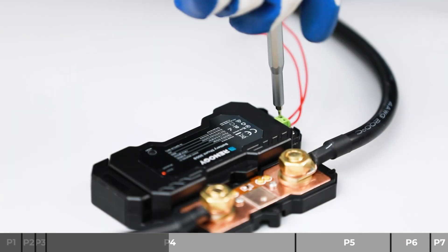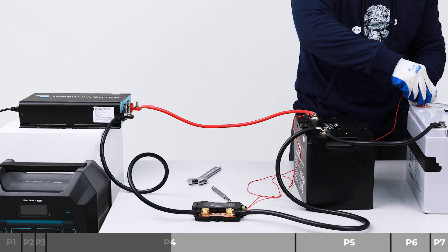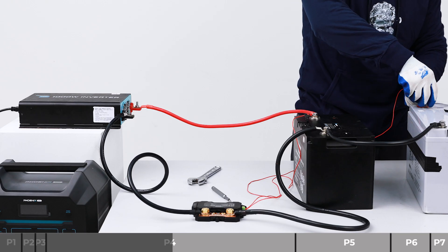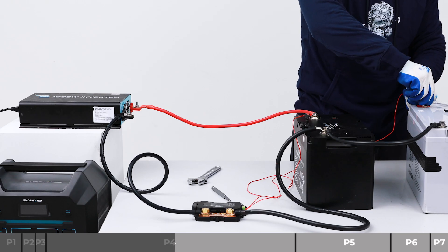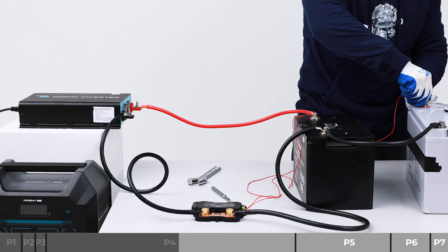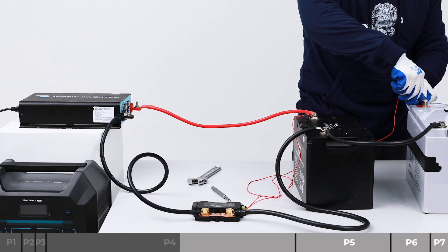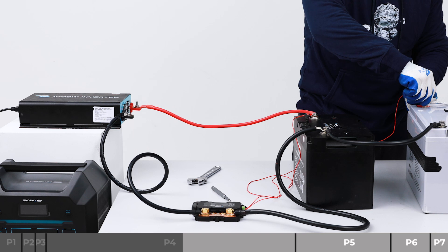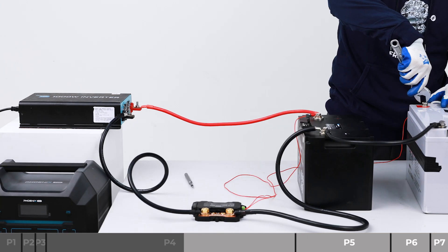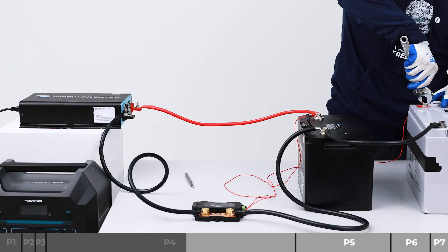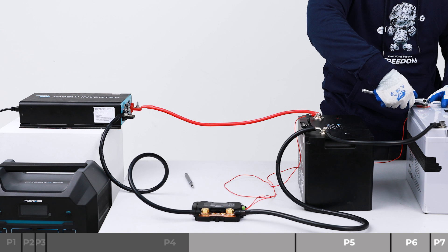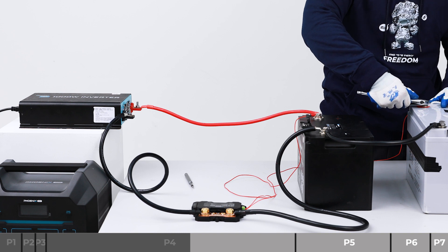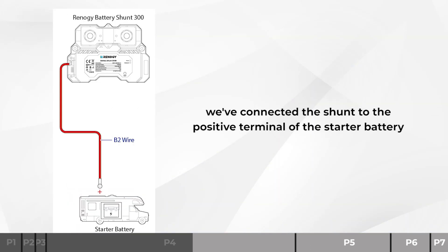Also, the battery shunt can be connected to the starting battery to get the starter battery voltage. Using a slotted screwdriver of 1 mm, install the B positive wire on the B2 terminal of the shunt. Install the B positive wire on the positive terminal of the starter battery. Now we've connected the shunt to the positive terminal of the starter battery.